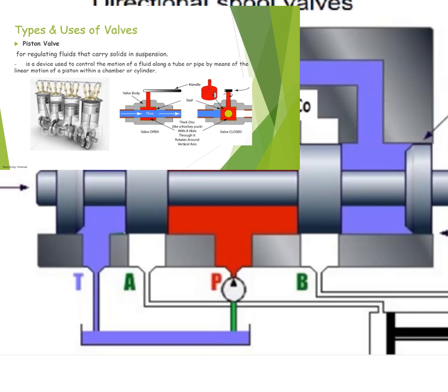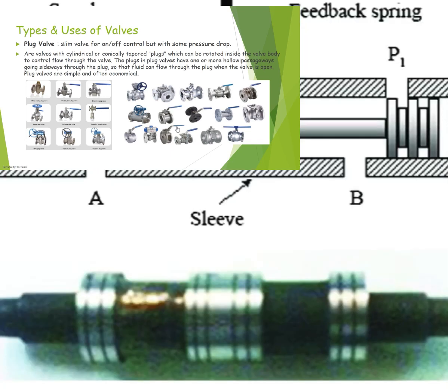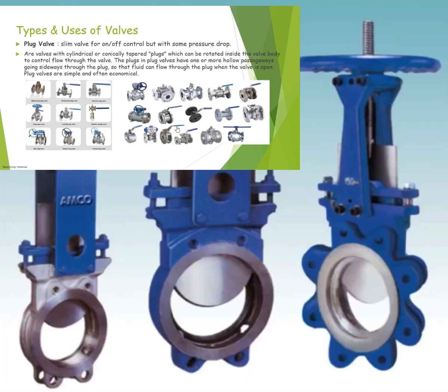A plug valve is a simple valve for on-and-off control but with some pressure drop. These are valves with cylindrical or conical tapered plugs which can be rotated inside the valve body to control the flow through the valve. The plugs in plug valves have one or more hollow passageways going sideways through the plug so that fluid can flow through the plug when the valve is open. Plug valves are simple and economical.